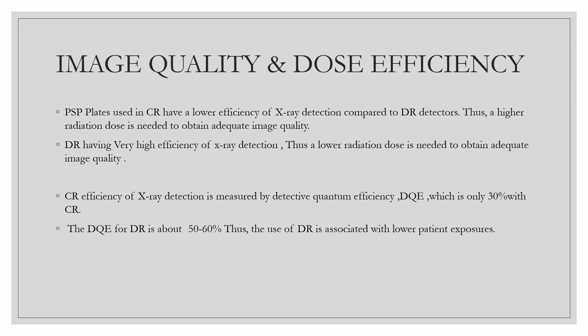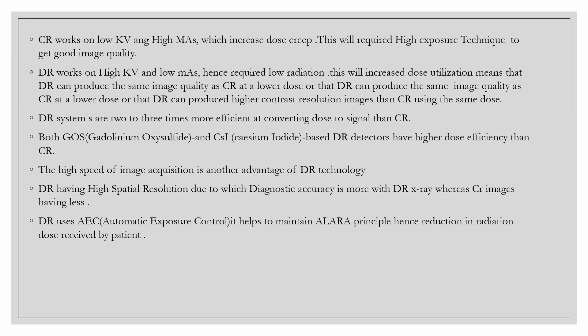In CR, efficiency of X-ray detection is measured by Detective Quantum Efficiency (DQE), which is only 30%. In DR, the DQE is about 50 to 60%. Thus, the use of DR is associated with lower patient exposure.